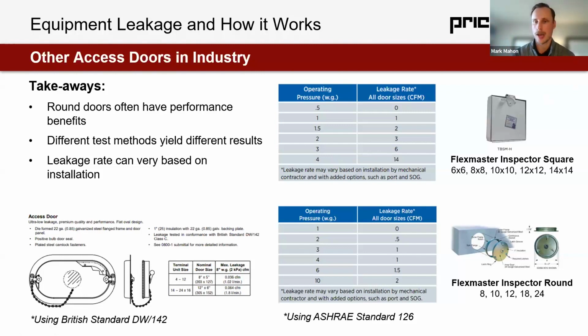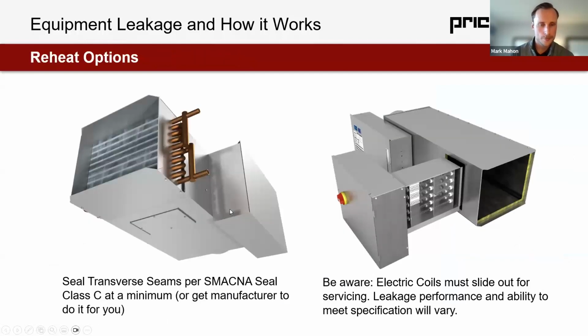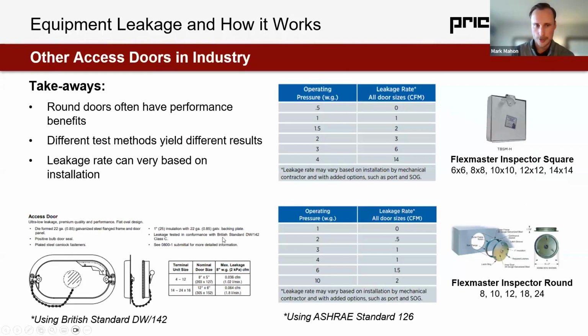ASHRAE Standard 130, which is our method, actually includes installation because we have leakage out of the seam of the door to the mate to the casing. So ASHRAE 130 is a little bit different. The bottom left, we have Naylor's door. Naylor's door is actually quite a good door. We're going to be building something somewhat similar, maybe a little bit more elevated too. They use a British standard, DW142. I'll be honest, I don't even know what that is, and I don't really know why they're using a British standard as a Canadian-American manufacturer. I don't know the implications that would have on the actual performance of the door when installed. And that is directly out of their spec, just for what it's worth.